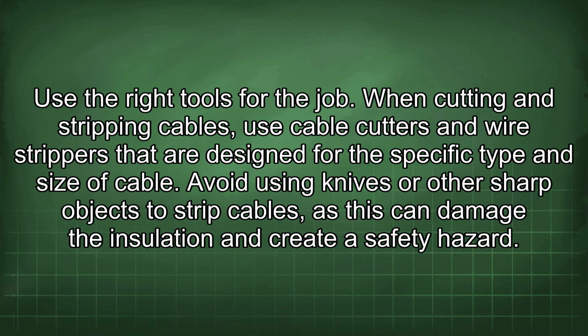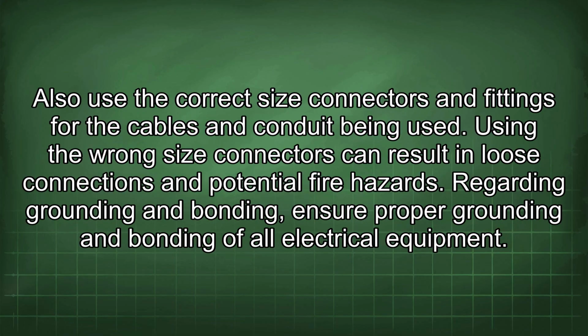When cutting and stripping cables, use cable cutters and wire strippers that are designed for the specific type and size of cable. Avoid using knives or other sharp objects to strip cables, as this can damage the insulation and create a safety hazard. Also use the correct size connectors and fittings for the cables and conduit being used. Using the wrong size connectors can result in loose connections and potential fire hazards.